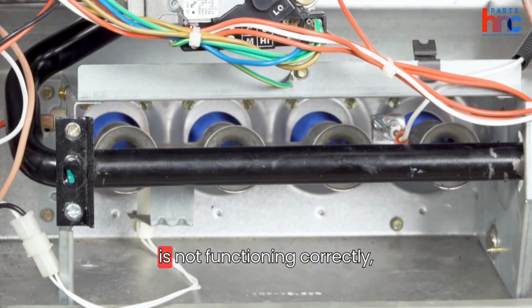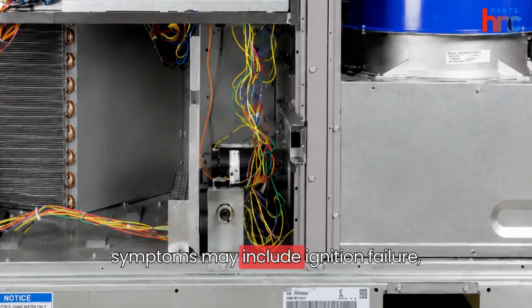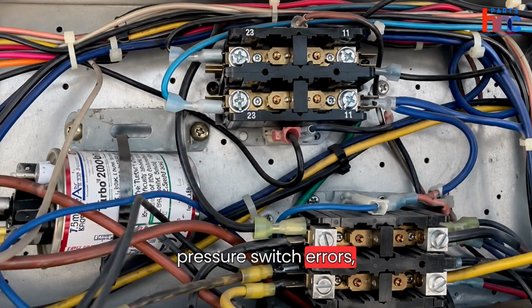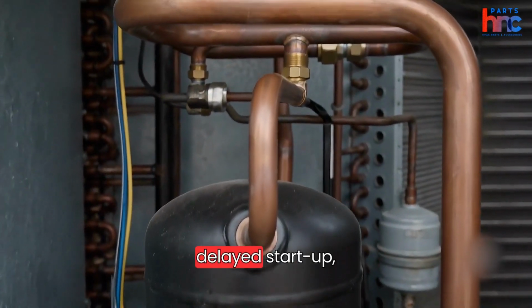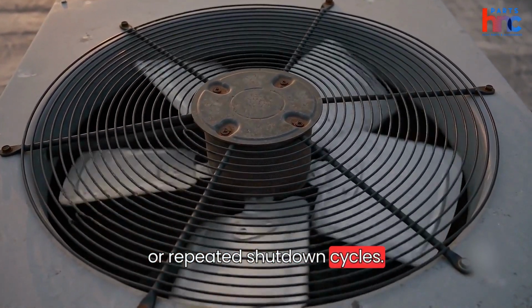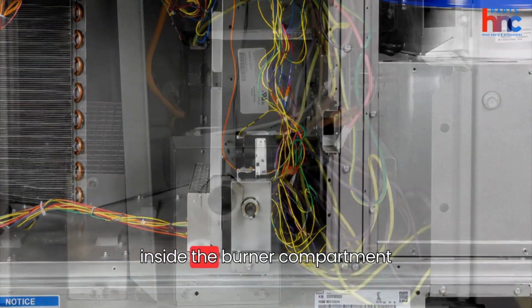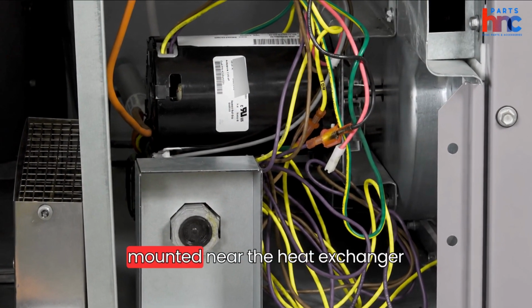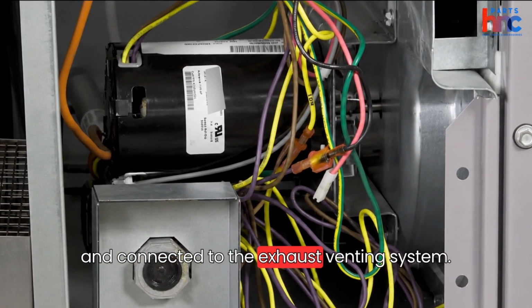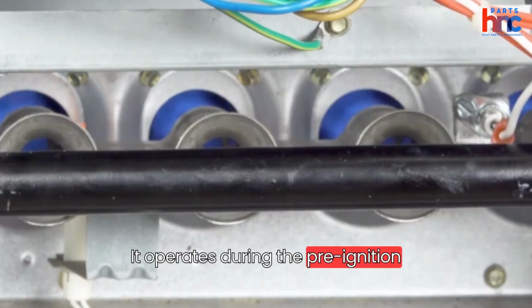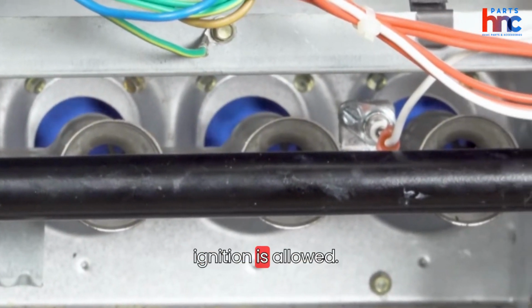When the inducer assembly is not functioning correctly, symptoms may include ignition failure, pressure switch errors, weak airflow, unusual noise, delayed startup, or repeated shutdown cycles. The inducer blower is located inside the burner compartment of the rooftop unit, mounted near the heat exchanger and connected to the exhaust venting system. It operates during the pre-ignition safety check before burner ignition is allowed.